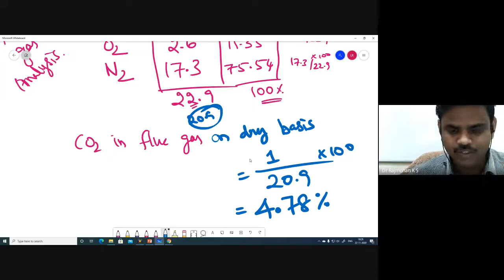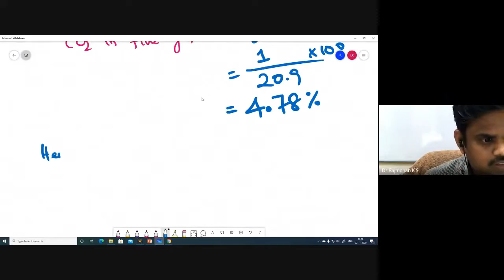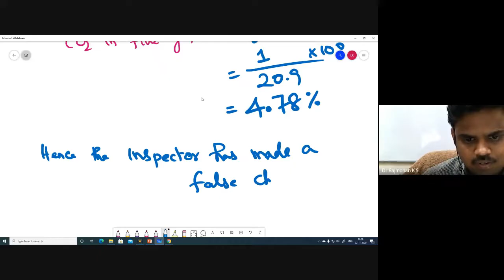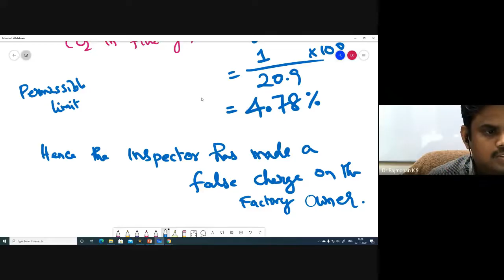What was the inspector's charge? He was saying it is beyond 15 percent, right? So CO2 is 4.78 percent, whereas the permissible limit is 15 percent. Therefore, the inspector's charge is false. The inspector has made a false charge on the factory owner. In this question, it is given that the permissible limit of CO2 is 15%, whereas our analysis, particularly the Orsat analysis here, gives us 4.78% CO2 in the flue gas. So the inspector has made a false charge on the factory owner.